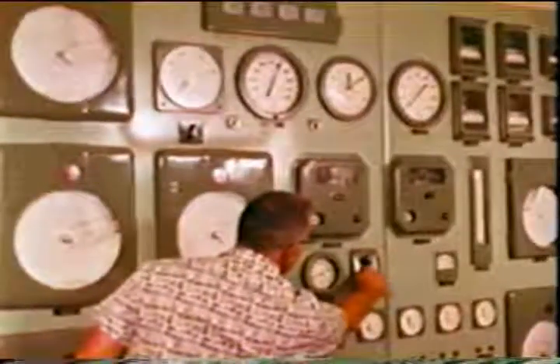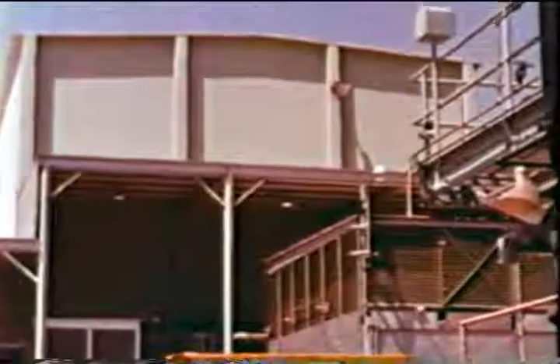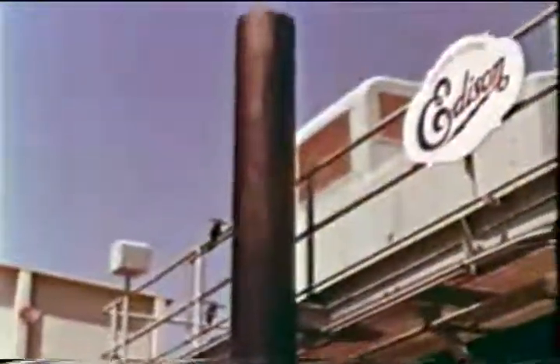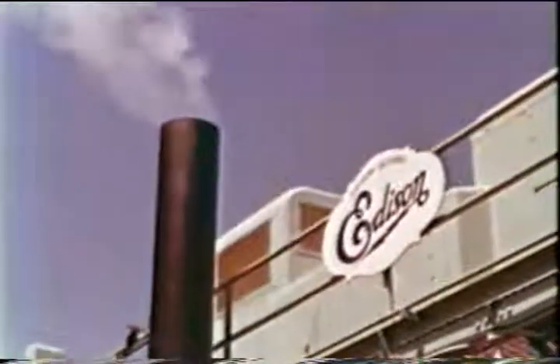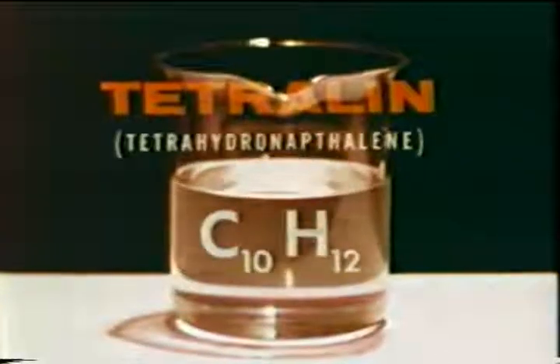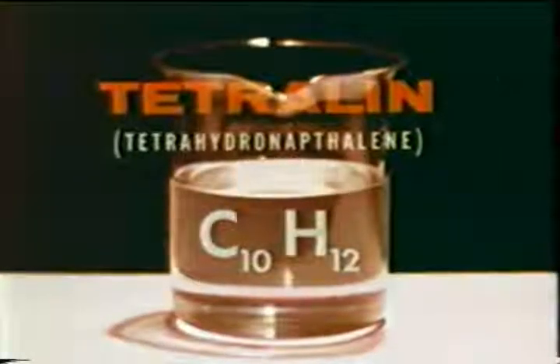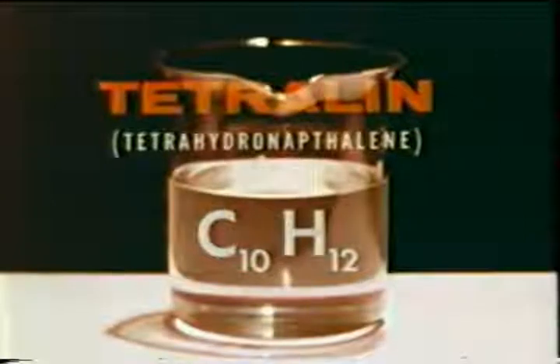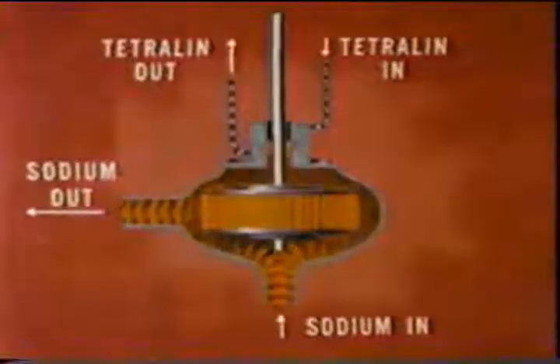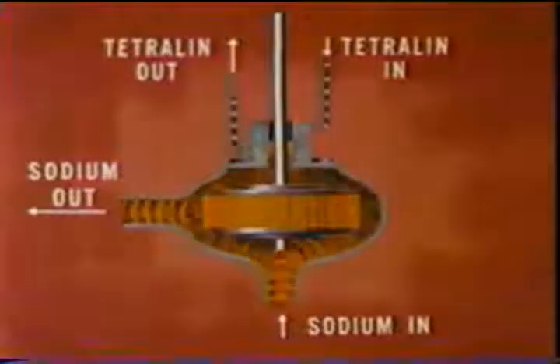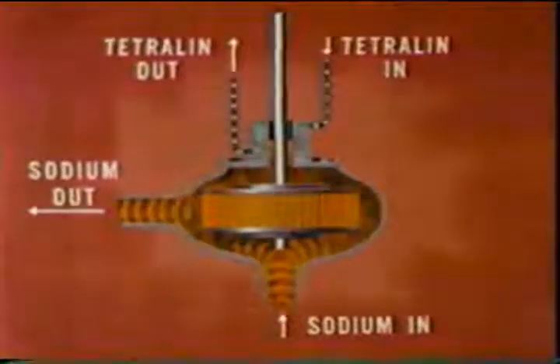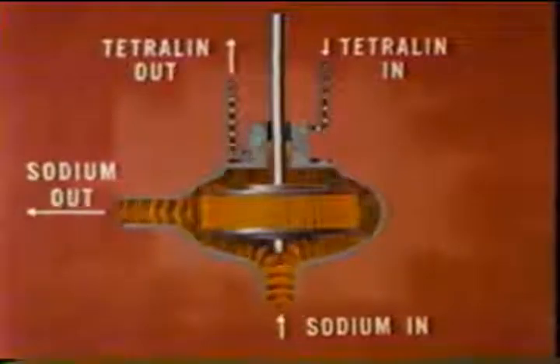Although designed to produce 825 degree Fahrenheit steam, steam temperatures as high as 1,000 degrees were produced in the Southern California Edison Company steam generator adjoining the SRE. An organic liquid known as tetralin was employed to cool certain SRE components which were in contact with sodium. In this connection, tetralin was used in the main primary sodium pump as the coolant for the shaft freeze seal gland.